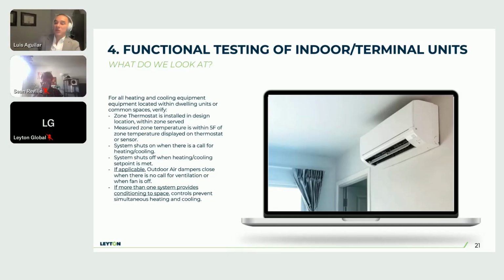So if we do have them in a new construction, then we do verify to make sure that the zone thermostat is within the zone. So these are typically single zones. So if they're serving one bedroom, for example, then we want the thermostat to be in that bedroom, right? That would make the most sense, as that's where we want the set point to be met. But you would be surprised, maybe that's not the case. Maybe the thermostat is not located within the zone. So we would not want that to be the case. So we definitely check for that. And then the thermostat controls themselves. We want to make sure that if you've ever seen one of these, sometimes they have the temperature located up in the corner, and they'll display the current zone temperature. So we want to make sure that's correct. If that sensor is not working correctly, then the system's not going to operate correctly.